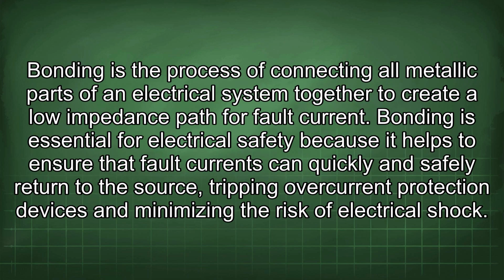Bonding is the process of connecting all metallic parts of an electrical system together to create a low impedance path for fault current. Bonding is essential for electrical safety because it helps to ensure that fault currents can quickly and safely return to the source, tripping overcurrent protection devices and minimizing the risk of electrical shock.